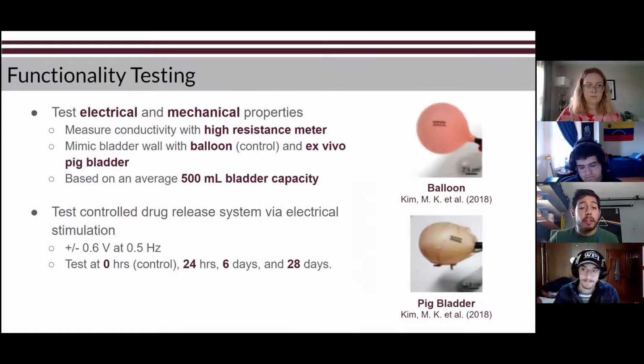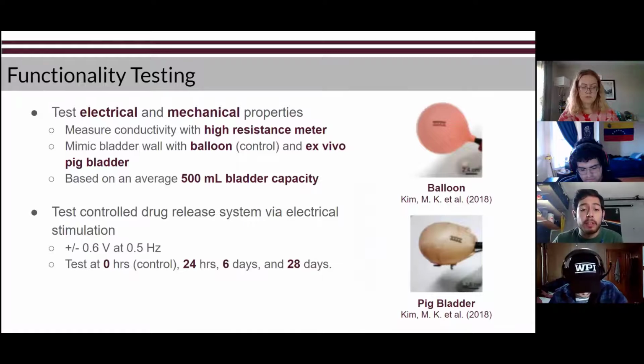Moving on from that, because our design is a drug release system, we would need to conduct a series of functionality tests to make sure that it's meeting the design requirements. In terms of the sensor, it will be tested in terms of electrical and mechanical properties. The conductivity will be measured using a high resistance meter, since the resistance is caused by a change in strain. A balloon and an ex vivo pig bladder will be used to mimic the bladder wall due to the similar elastic properties to the actual detrusor wall in humans. And then finally, the average of around 500 milliliters for a maximum bladder will be used to make the calculations for the force sensor and make the setting for the full bladder for the patient.